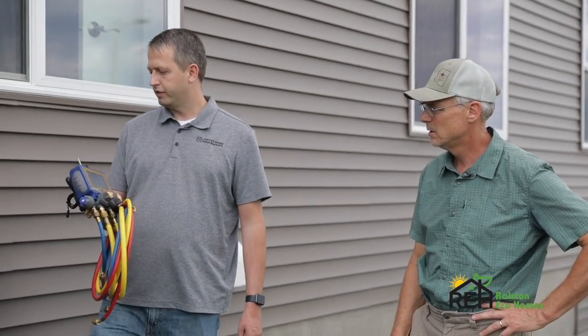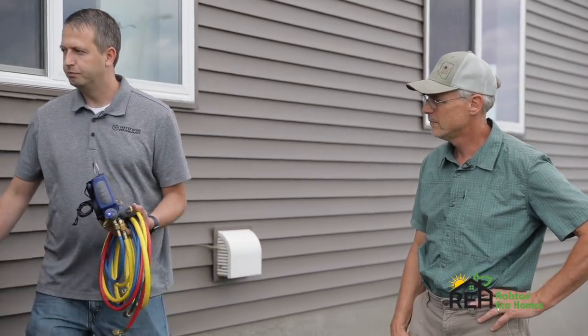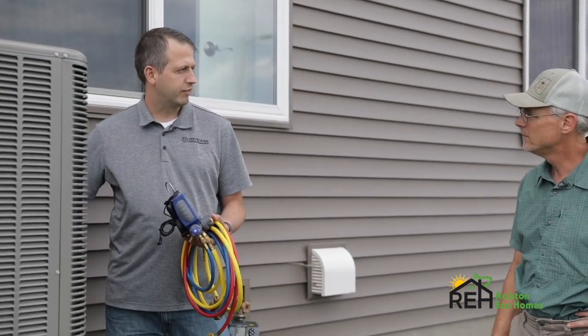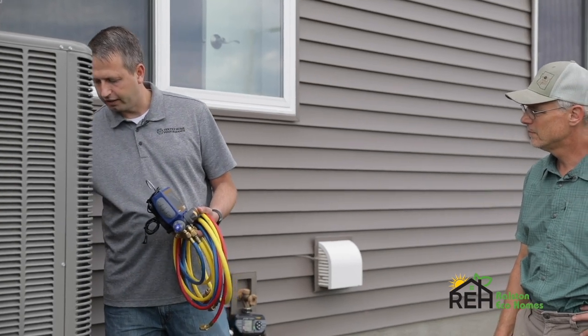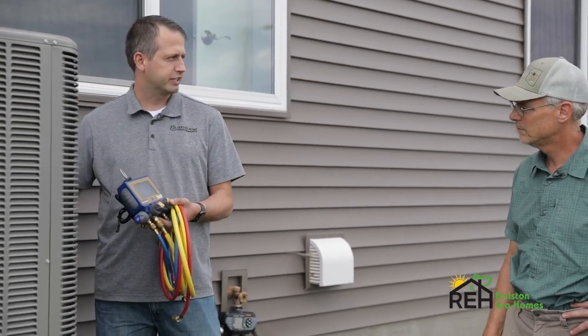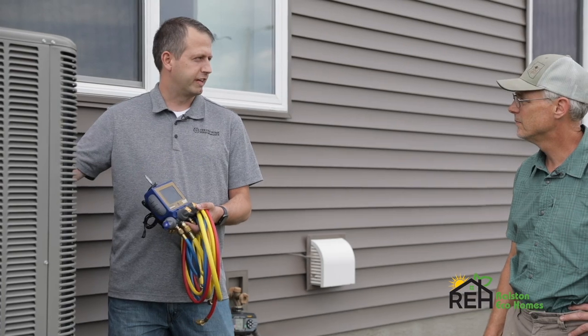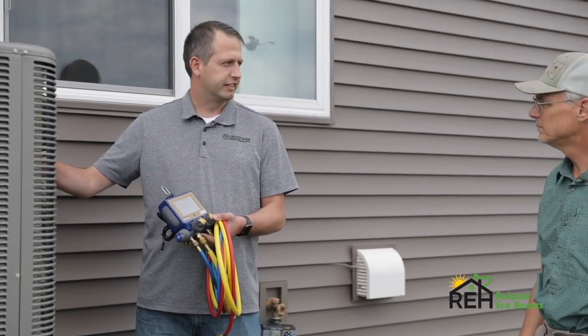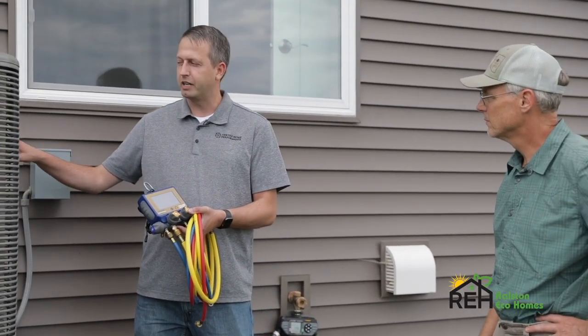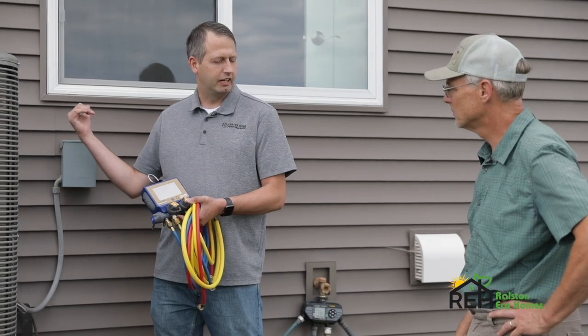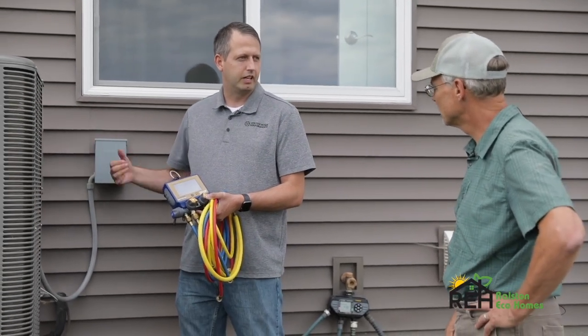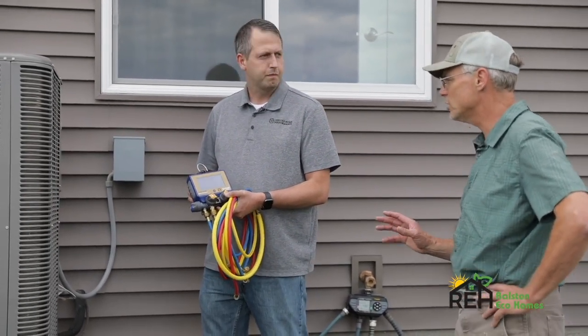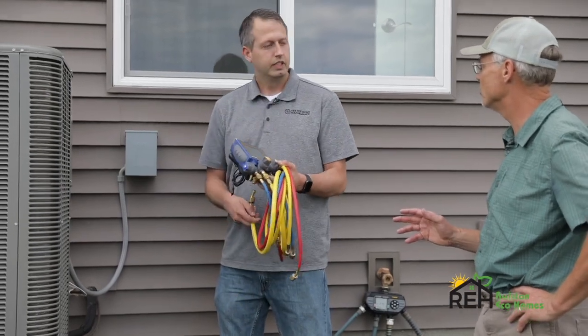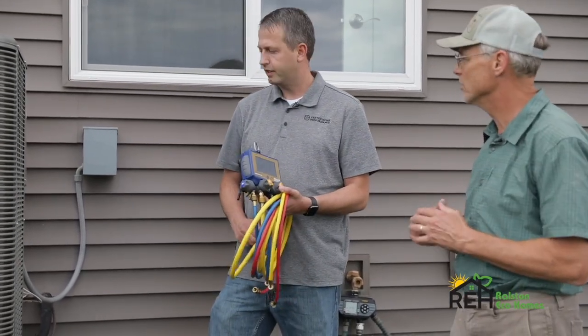Yeah, so we use these digital sets of gauges here. We're going to measure the pressures of the liquid and suction line on the air conditioner, and also the temperatures, and then compare it to the manufacturer's data. And then if it needs any adjustment, we'll adjust it to the right pressures, and then we'll get hopefully better temperatures inside than what we have now. And the way you adjust those pressures is by adding or removing refrigerant. Yep, that's correct.